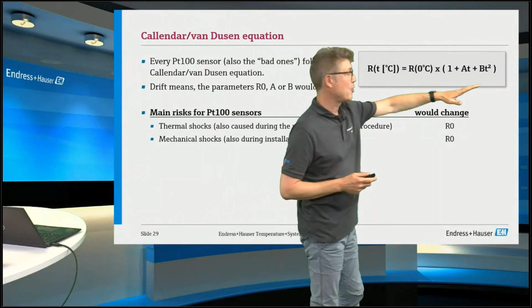The same will happen for mechanical shocks. If your sensor falls down, there might be some mechanical stress on the PT100 itself. It will react in a way, and again, multiplied to the bracket, the complete curve will be different. So talking about the main factor here, it is the A, which is more or less the inclination of the characteristic line curve. And you can change this factor A mainly by high temperatures.